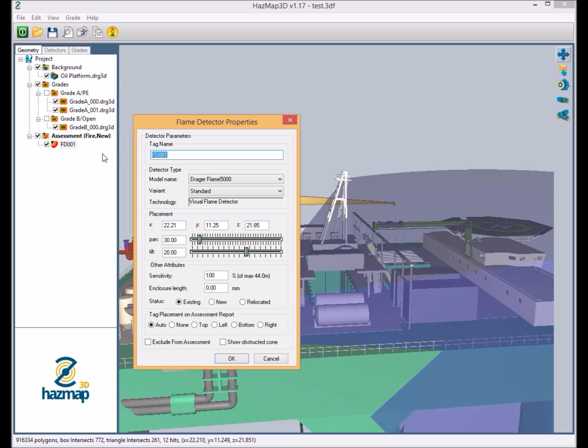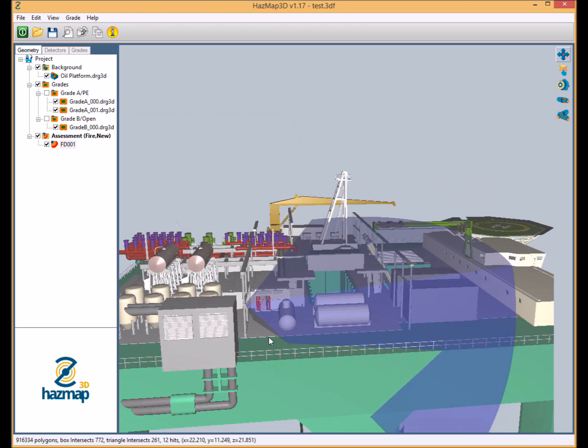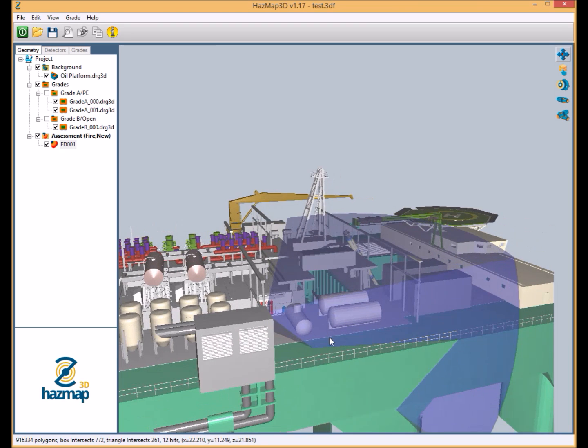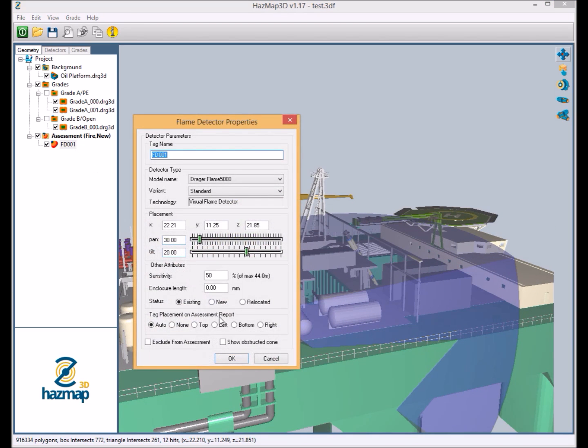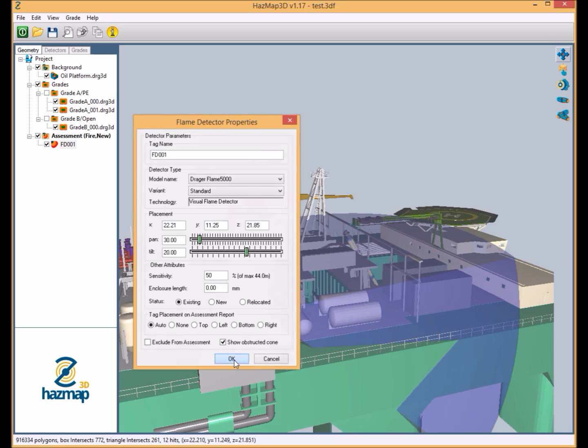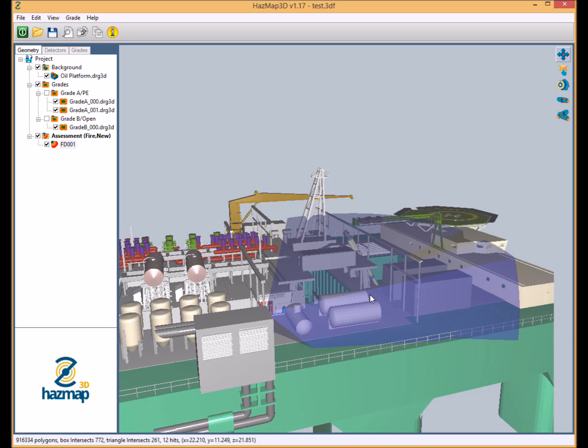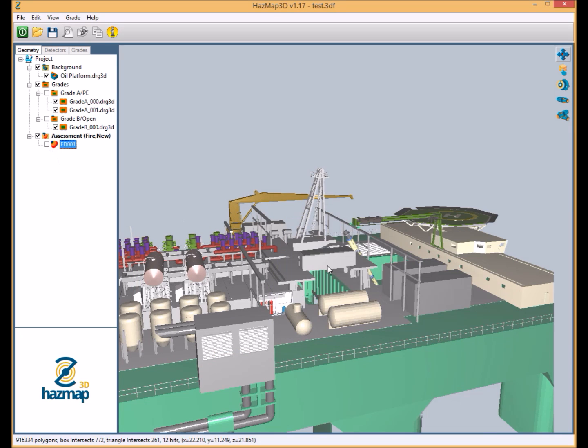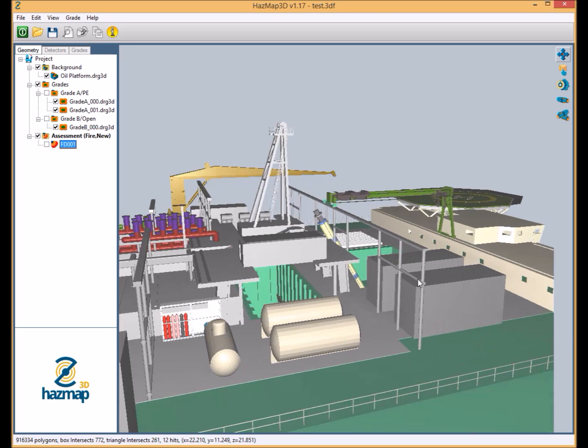And what it does is it gives the user the most accurate flame detection assessments on the market. So for the purpose of this assessment, we're just going to reduce the sensitivity of the device down to 50% of the maximum 44 meters, which is taken from the detector data sheet. And this is just to keep the field of view within the 3D model to keep the example nice and tidy. Okay, so we're happy with that detector location.